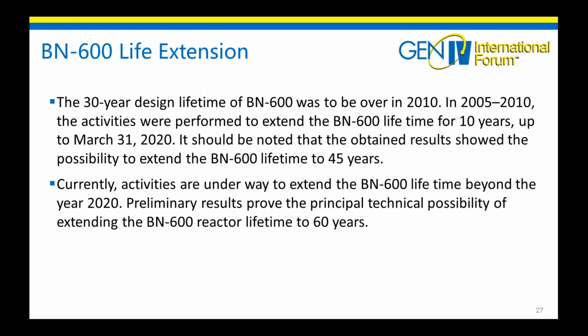The 30-year design lifetime of BN-600 was to be over in 2010. From 2005 to 2010, activities were performed to extend the BN-600 lifetime for 10 years, up to March 31, 2020. It should be noted that the obtained results showed there is a possibility to extend the BN-600 lifetime to 45 years. Currently, activities are underway to extend the BN-600 lifetime beyond the year 2020. Preliminary results prove the principal technical possibility of extending the BN-600 reactor lifetime to 60 years. It depends only on the replacement of equipment.